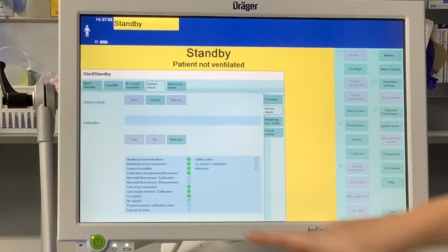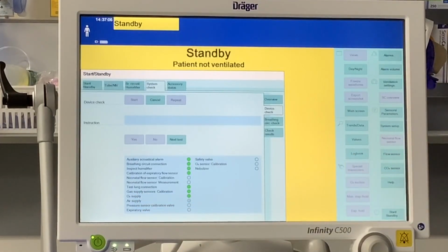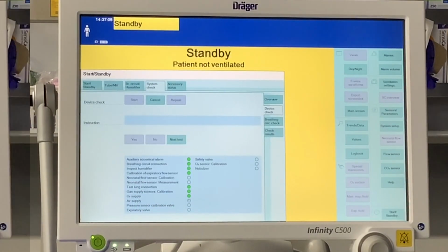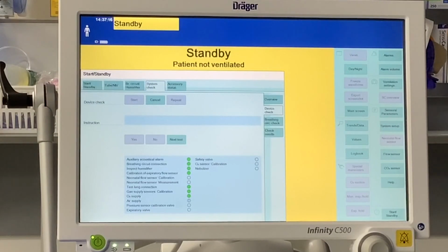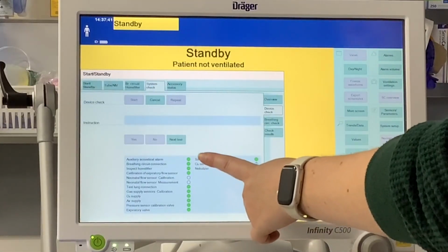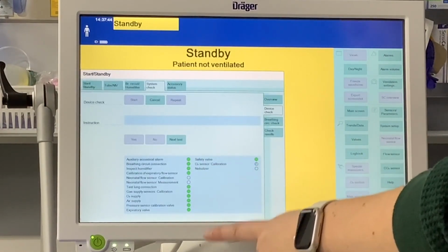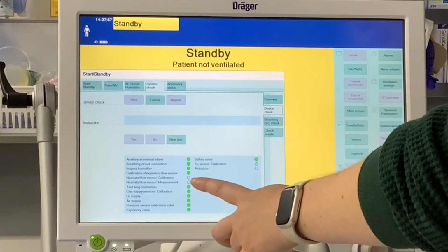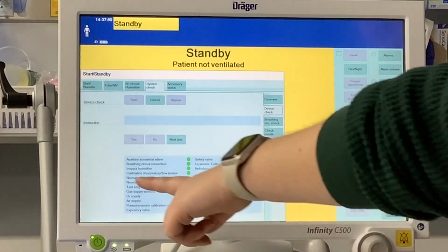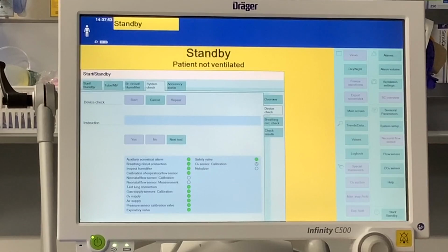You'll see O2 supply, air supply, so it does need to be hooked up to do that, as I previously mentioned. And once it's done these 2 checks, it goes through the rest quite a bit faster. And you'll see it's still moving on. In here, green obviously means it passed the check. If it was red, it would have failed. And when it's blank like that, it just means that we didn't do it, which we did say no, we didn't want to do the neonatal flow sensor. Now we're just waiting on the last 2 checks.